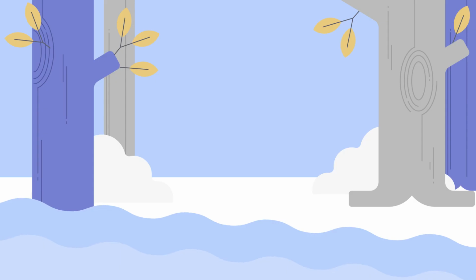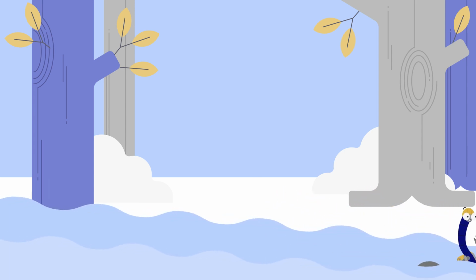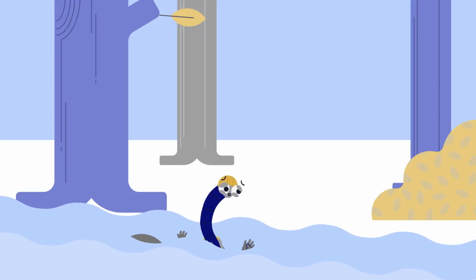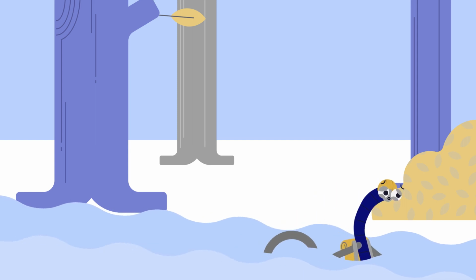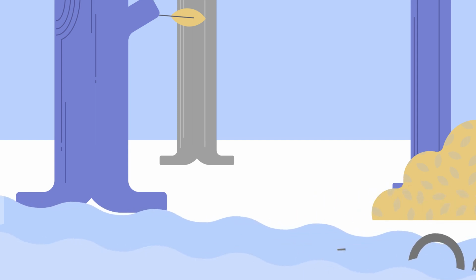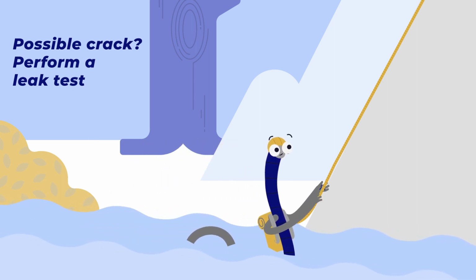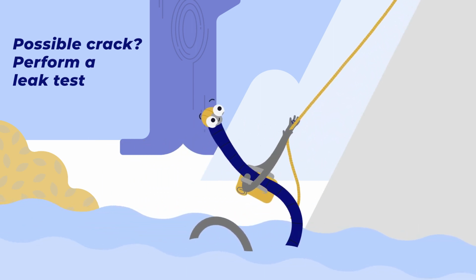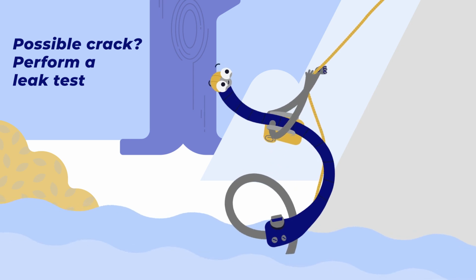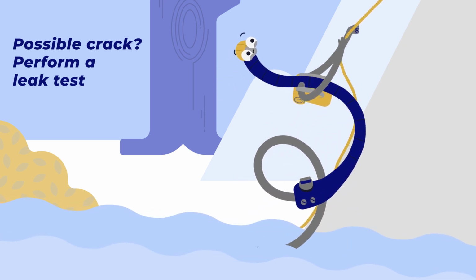Your Olympus scope is waterproof. However, even tiny cracks on the distal end may result in fluid invasion, causing serious damage to the internal electronics. That's why it's important to inspect the distal end before every use to avoid damaging the equipment. If you think you see a crack, don't use it and perform a manual leak test to confirm, or you could end up with an expensive and time-consuming repair from a flooded scope.